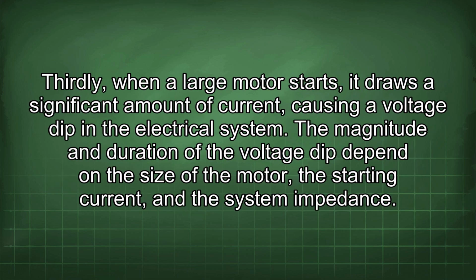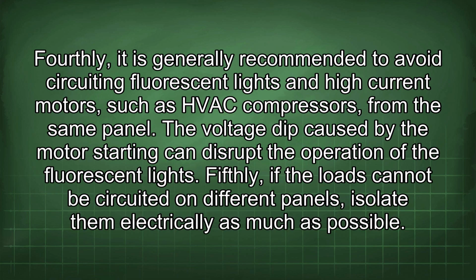Thirdly, when a large motor starts, it draws a significant amount of current, causing a voltage dip in the electrical system. The magnitude and duration of the voltage dip depend on the size of the motor, the starting current, and the system impedance. Fourthly, it is generally recommended to avoid circuiting fluorescent lights and high-current motors, such as HVAC compressors, from the same panel. The voltage dip caused by the motor starting can disrupt the operation of the fluorescent lights.